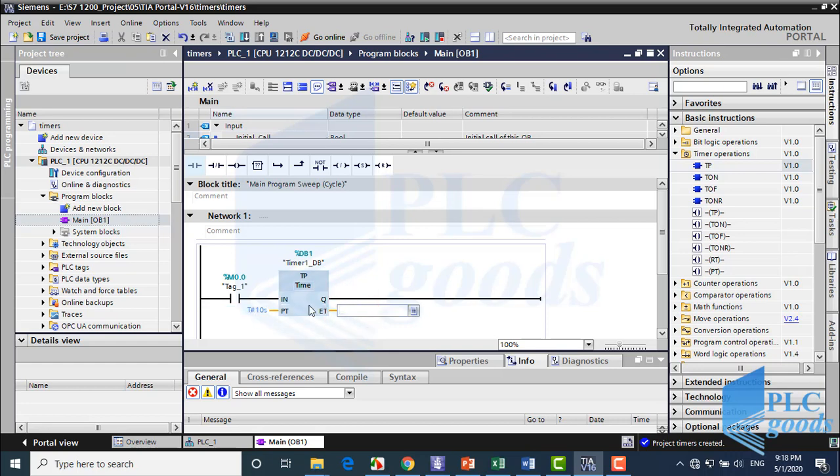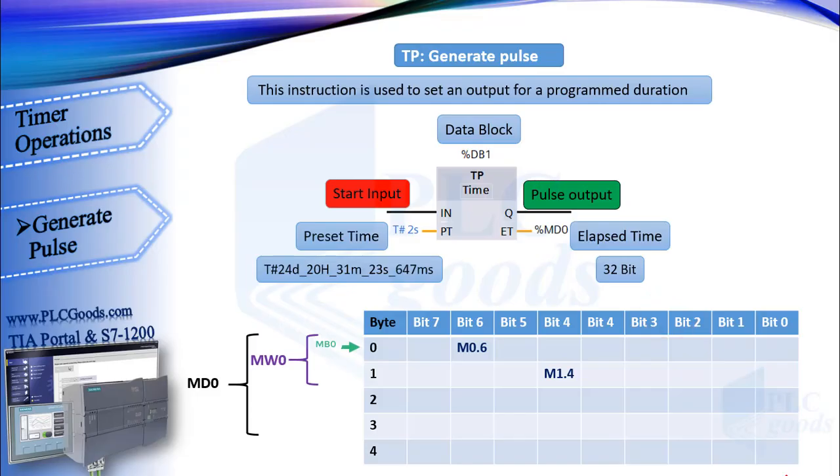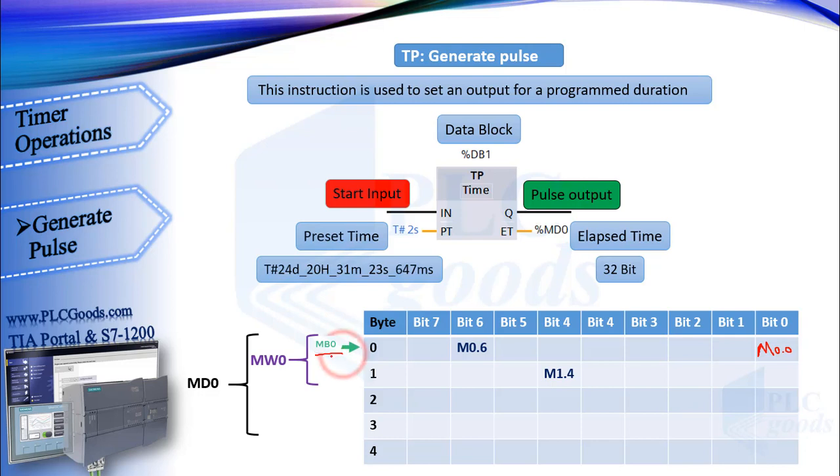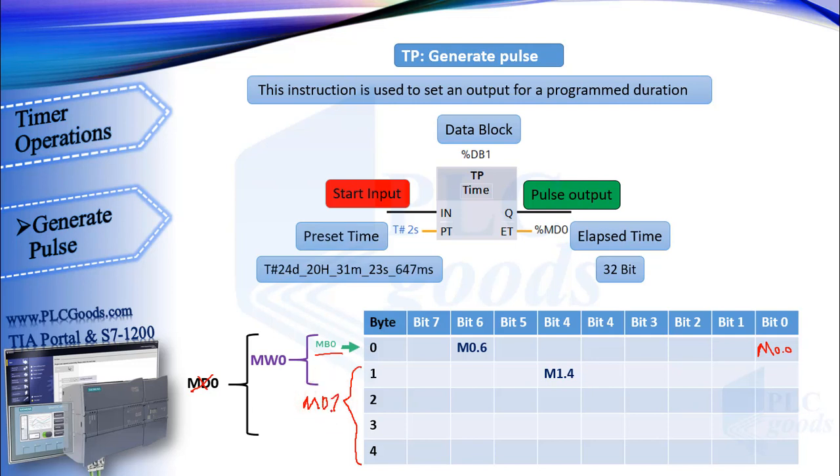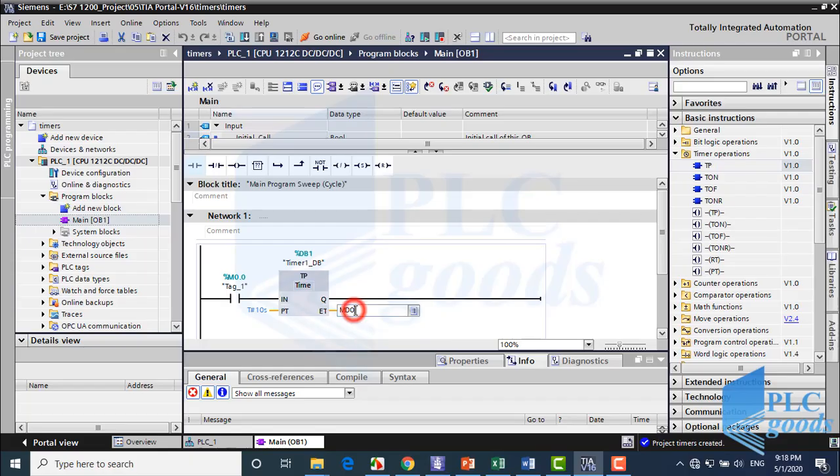Here I want to store elapsed time on PLC memory. I can't use MD0 because of this used memory M0.0. Let's see this table again. M0.0 is here in byte 0. I can't use MD0 because M0.0 is a bit of this address. But all bits of the MD1 are free, so I can use MD1 for the timer. So I write MD1.